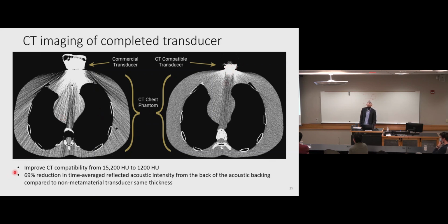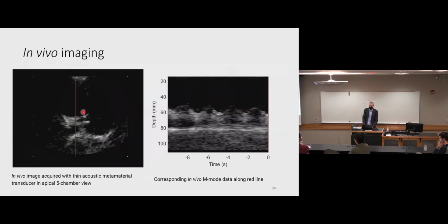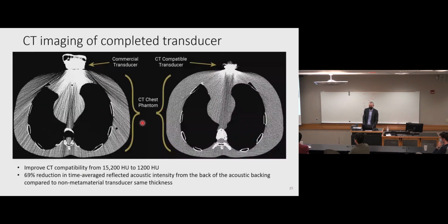So the other feature that we really care about is the acoustic performance. And so I mentioned earlier there's that reflection from the back wall that could produce an artifact in our image. And what we see is that if we use our acoustic diode design, we're able to reduce the amplitude of that reflection by about 70%. And so, again, it's not a perfect ultrasound image like we saw here, but we think it's acceptable for the gating goal that we have.